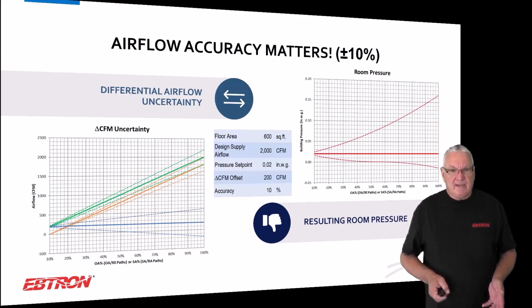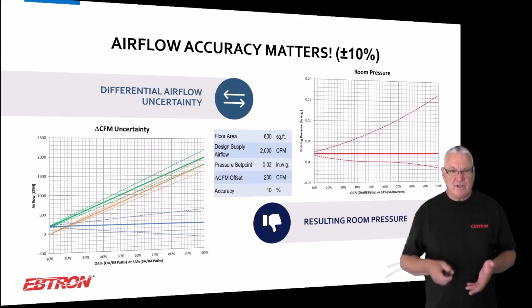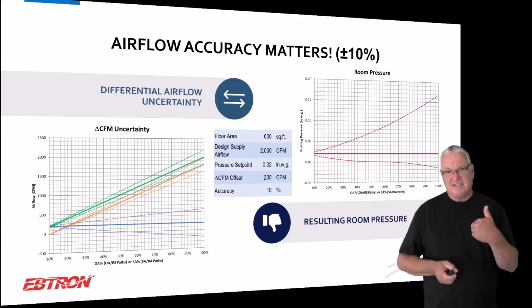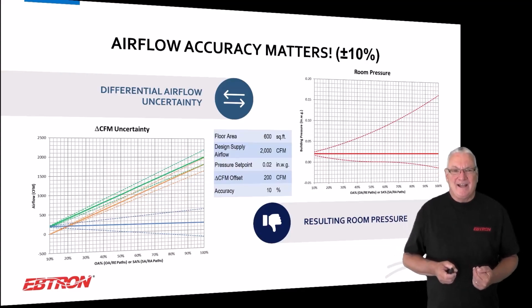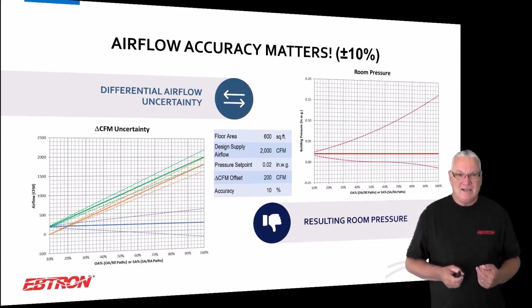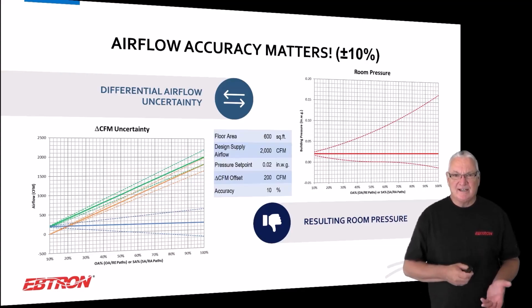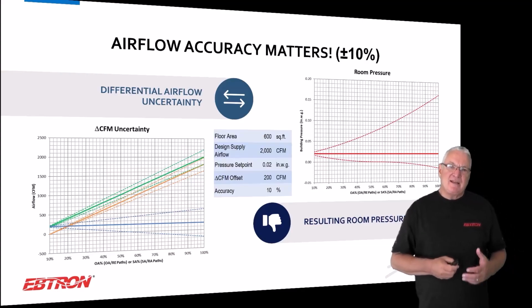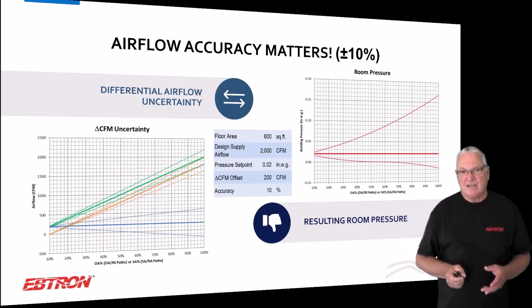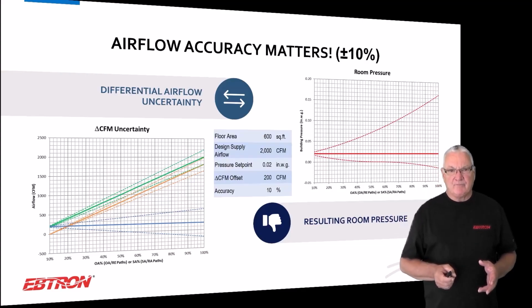Okay. I mean, in this case here on the left, the solid lines are what you theoretically think you have in flow when you finally sit down and look at this. And then the dashed lines are the uncertainty, plus or minus uncertainty. And if you look at that bottom left graph, you can be really positive or really negative. And what I've done is I've just made an assumption, which may or may not be right, that the relationship of pressurization flow to pressure is a square root relationship.